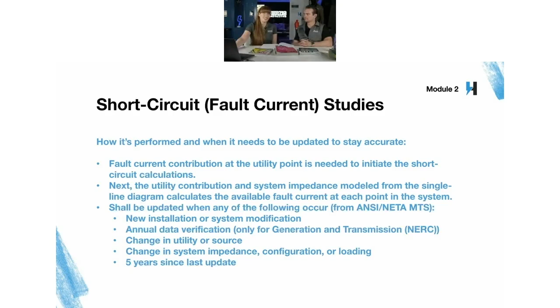So 5 years at a minimum, or you shall update it anytime there's a change that could affect the results of the study. So the whole should versus shall thing, right? A lot of times people have said that it's best practice. It's good to keep up to date on your one-lines and your studies. Well, it's a shall, actually. It shall be updated whenever there's a change.